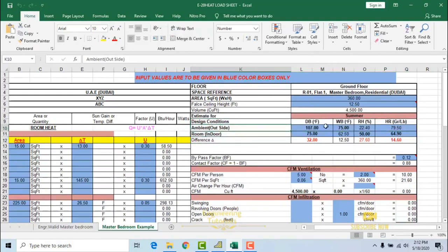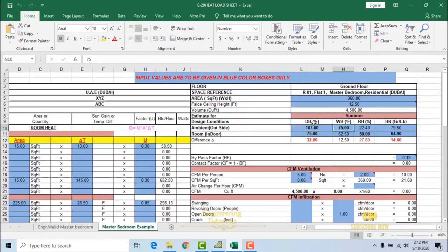Let's say this is a building located in Dubai. The outdoor design condition for Dubai is a dry bulb temperature of 107 degrees Fahrenheit and a wet bulb of 75 degrees Fahrenheit. These values can be obtained from local authorities in your location — in Dubai, this is provided by the Dubai Municipality.